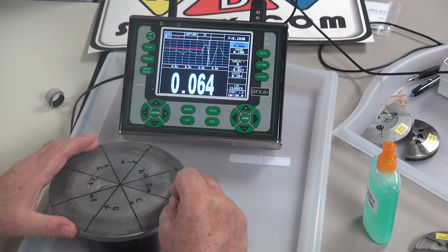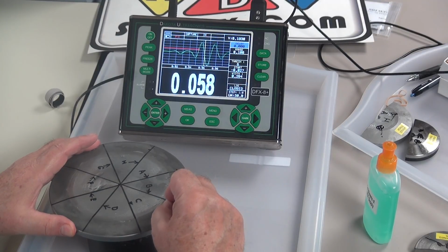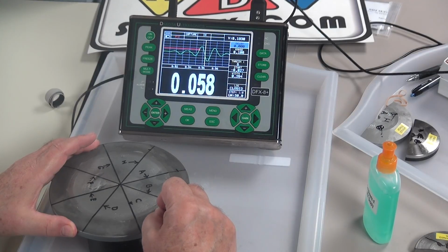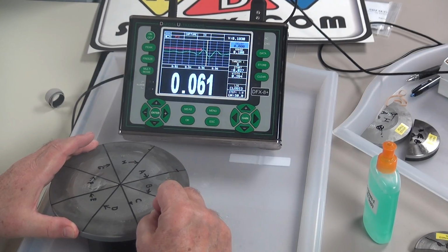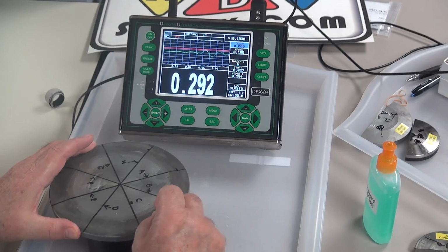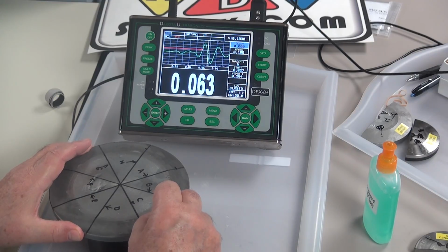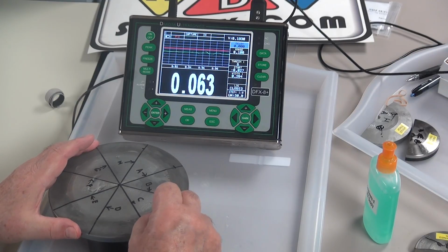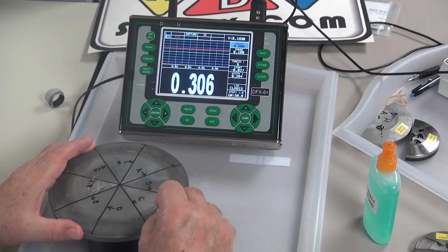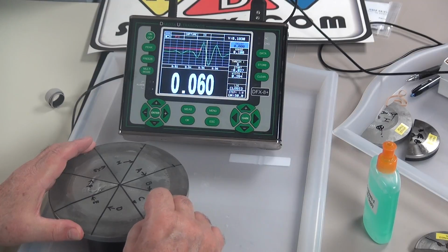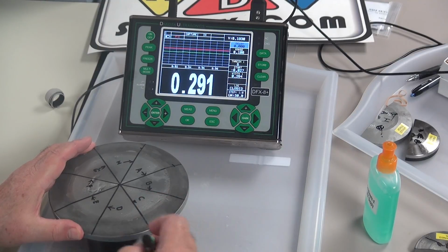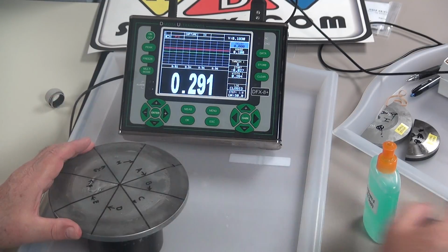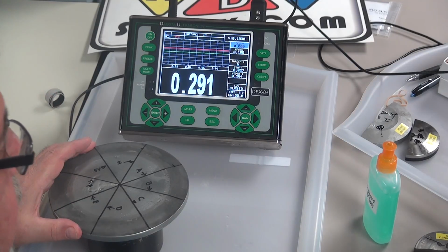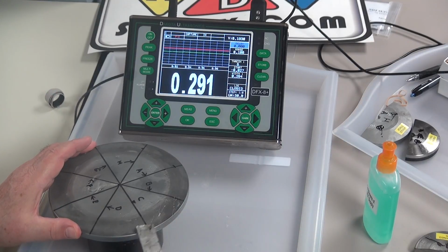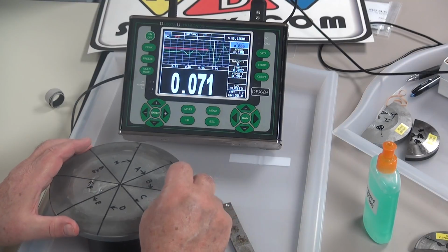I didn't like that variation of measurements. I want to make sure that it wasn't me, so I'm coming back. We're seeing the measurement drop a bit. There's an area here where I'm losing couplant, and that's a mechanical couplant issue, so I'm just going to smear some more couplant on here.